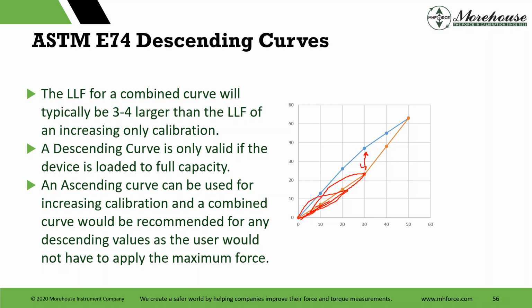And then it's one of those things. If you cannot go to capacity each time with the combined curve, you're just going to live with a larger lower limit factor, which is going to give you a larger uncertainty for ascending and descending. An ascending curve can be used for increasing calibration. We always recommend doing that.